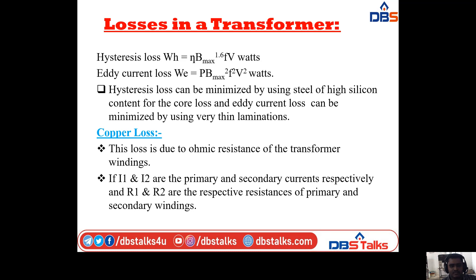The hysteresis loss Wh = η·Bmax^1.6·f·volume. The hysteresis loss can be minimized by using steel of high silicon content for the core. The eddy current loss can be minimized by using very thin laminations.